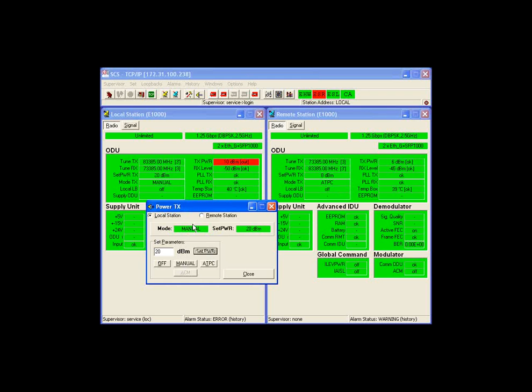Now I still have some space. In this case I'm using 4 dB, but maximum is set to 10 dB, so I have an additional 6 dB. Here it's not so good, because it's 8 dB and 6 dB is used, so I have just 2 dB. This is because I set it this way, but to have full functionality, the maximum power, I have to set it to 10 dB, then set 20 dB as power level, and then return back to ATPC.